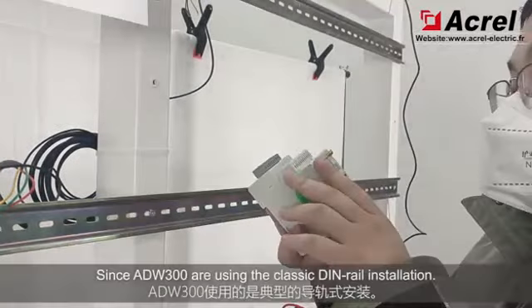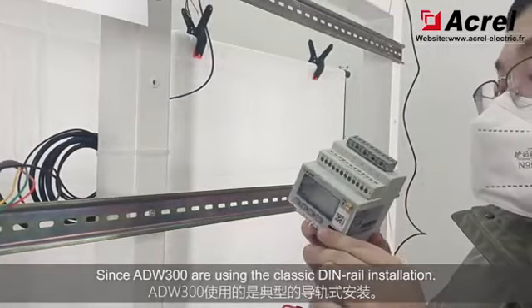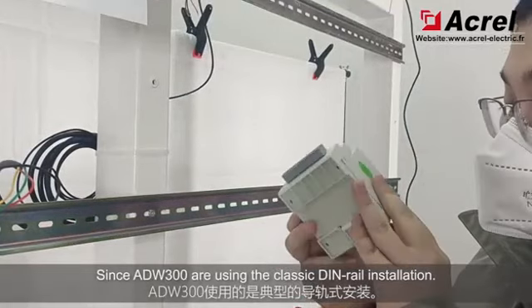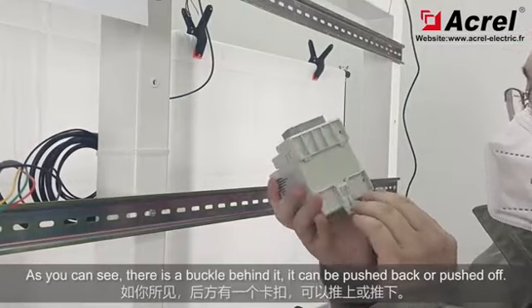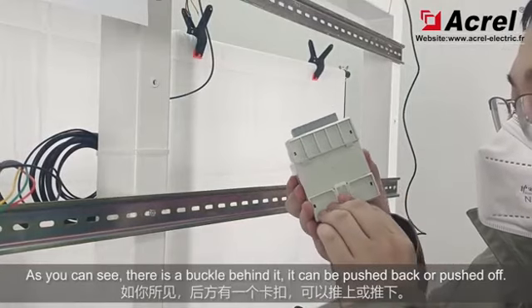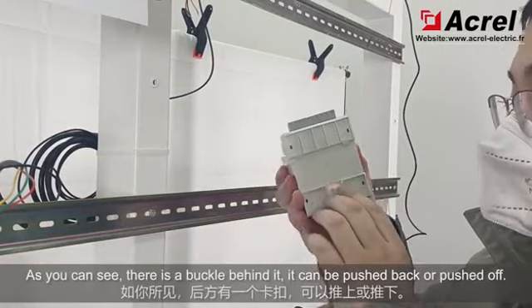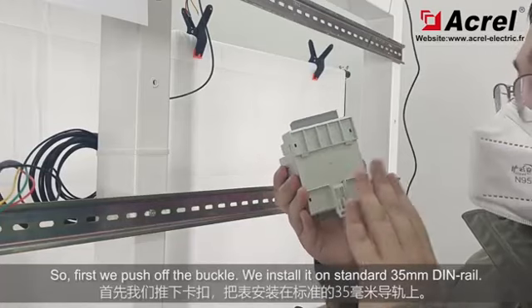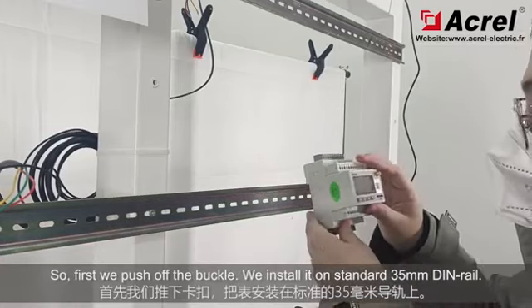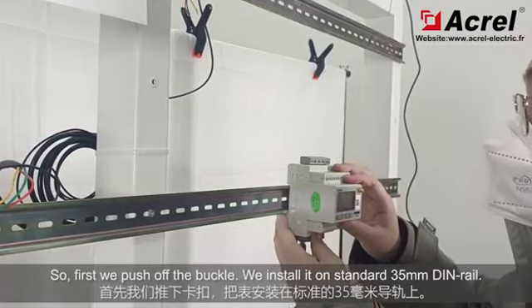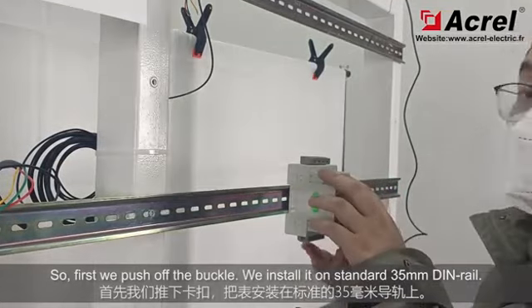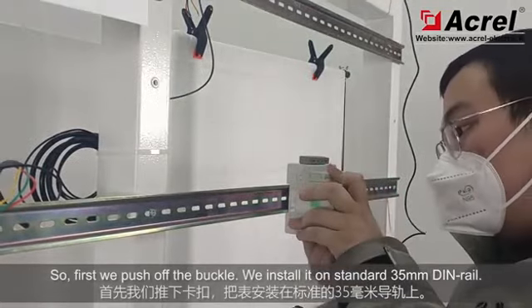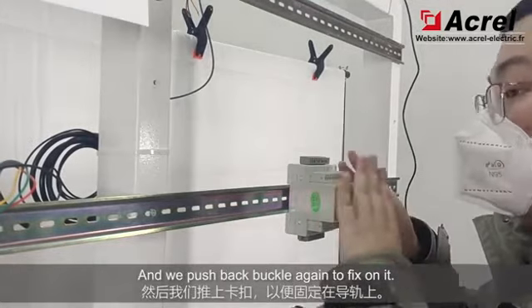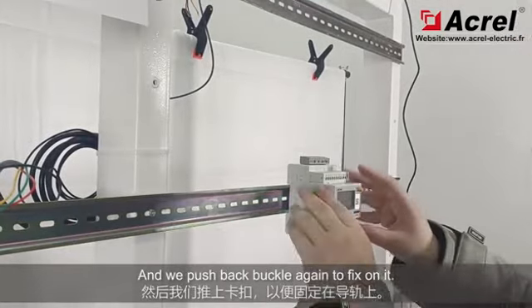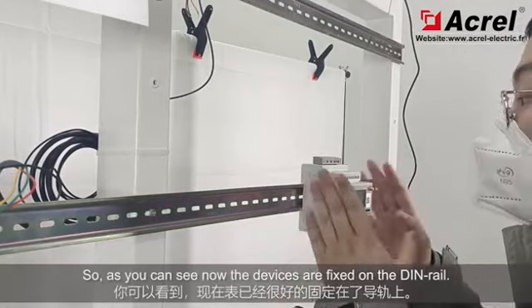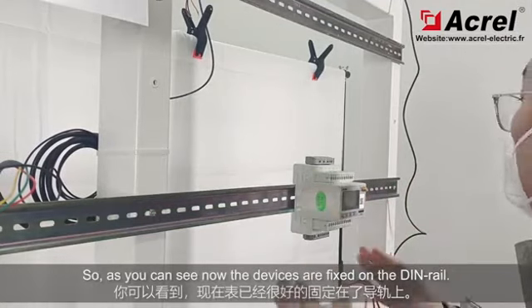Since the ADW300 uses the classic DIN rail installation, as you can see there is a buckle behind it that can be pushed back and pushed off. So first we push off the buckle, install it on a standard 35mm DIN rail, and push back the buckle again to fix it. Now, as you can see, these devices are fixed on the DIN rail.